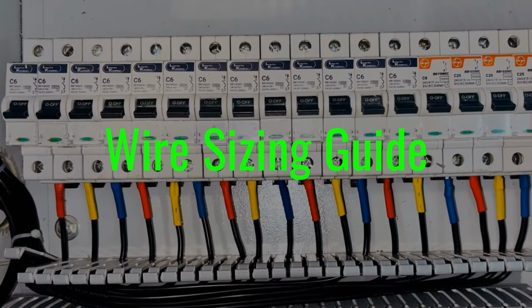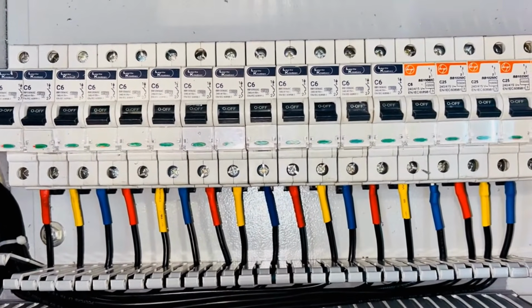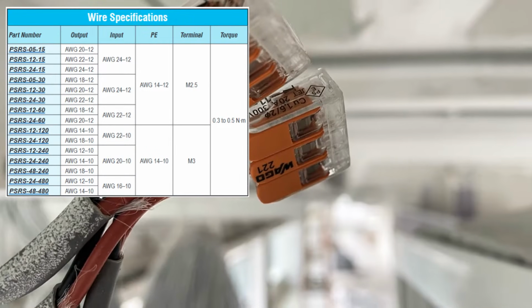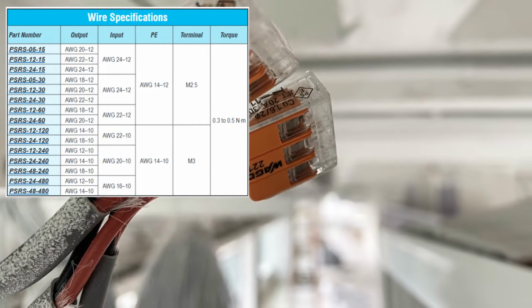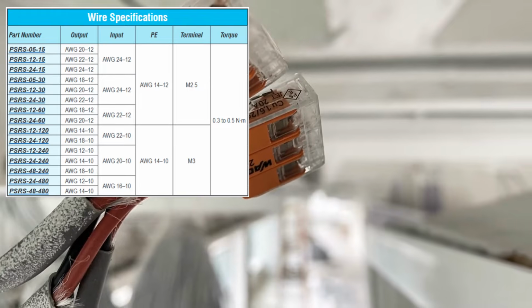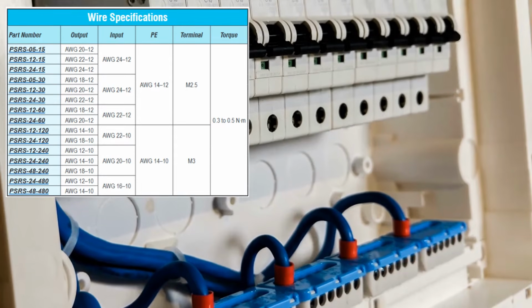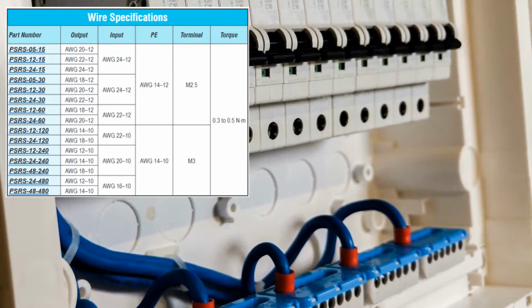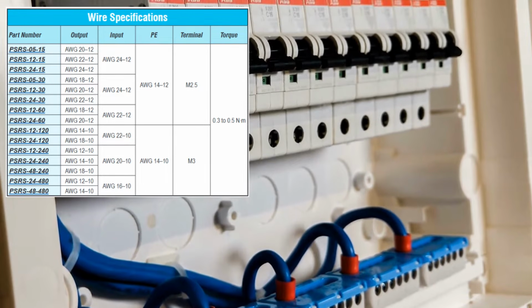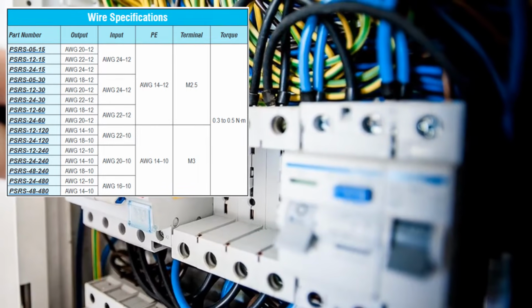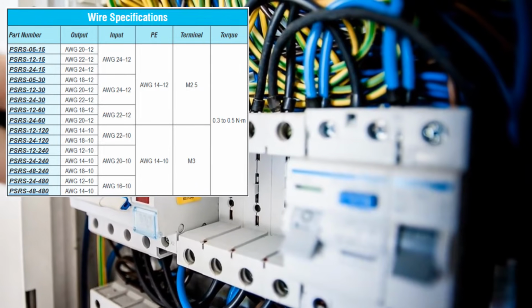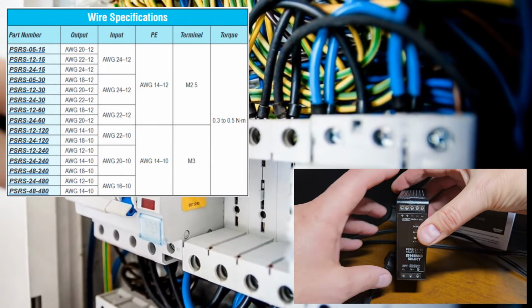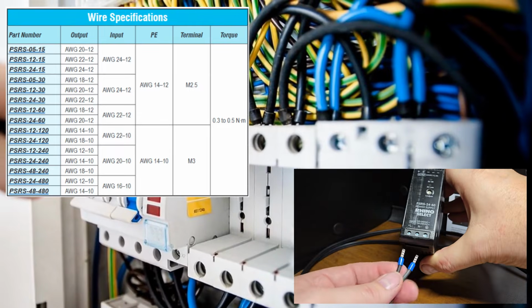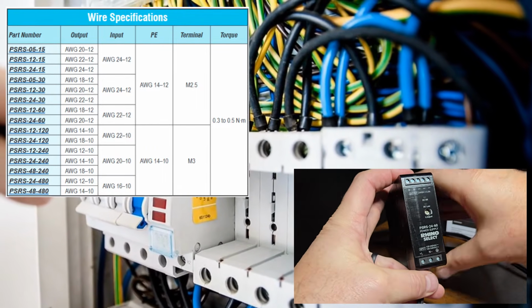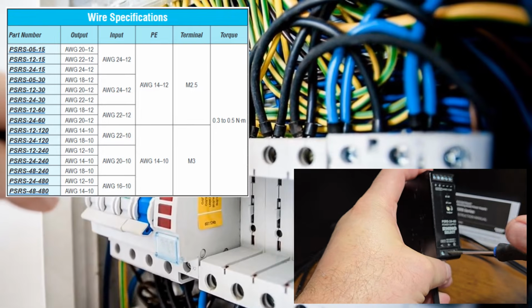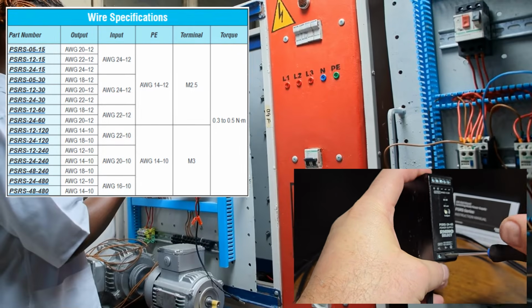Wire sizing guide. Selecting the correct wire size is crucial for safety and performance. Using a wire that is too small for the current load can lead to overheating, voltage drops, and potential fire hazards. Below is a general guide for typical copper wire ampacity used in control panels. Note, this chart is for general guidance only. Always consult local electrical codes, such as the NEC in the US or CEC in Canada, wire manufacturer specifications, and consider factors like ambient temperature, wire insulation type, and number of conductors in a raceway when making a final selection.